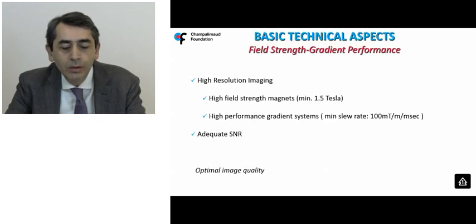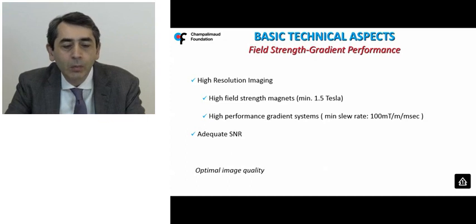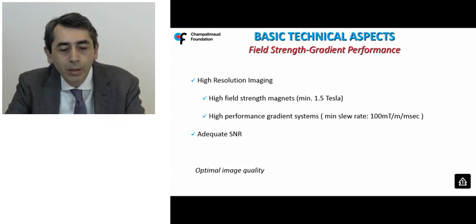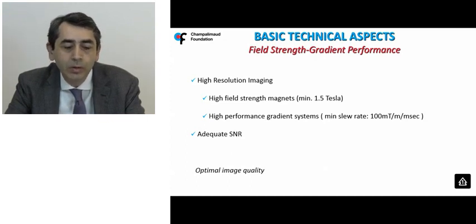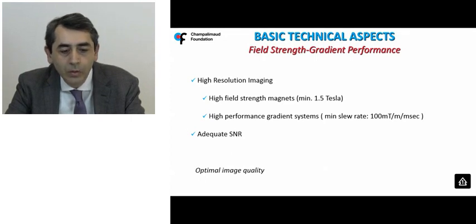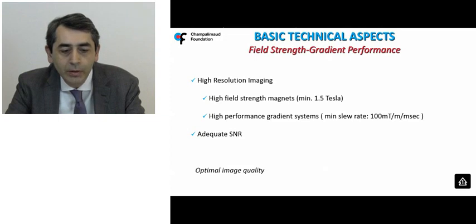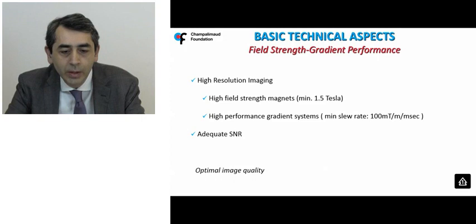In order to guarantee optimal image quality, one has to think about high-resolution imaging coupled with adequate signal-to-noise ratio. Entry-level specifications to fulfill these requirements include using at least 1.5-Tesla MRI scanners and, most importantly, utilizing high-performance gradient systems.